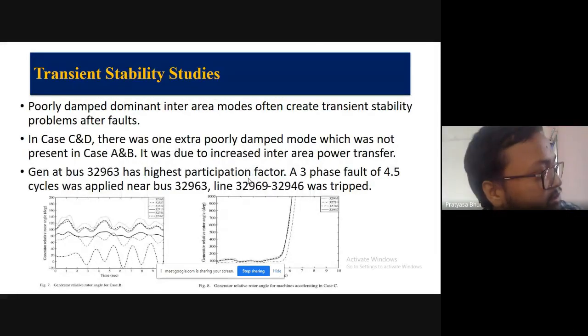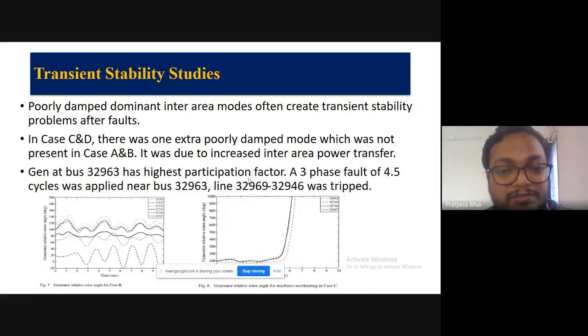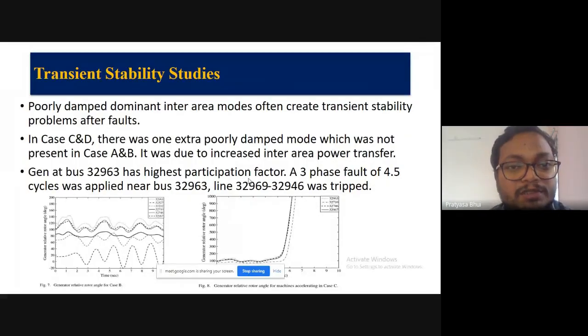Now, the study we are doing for small signal stability will help us to study transient stability in some cases, because sometimes we have weak, dominant inter-area modes where the frequency is very low and damping is poor. In those cases, sometimes if there is a fault, it excites that mode. In that case, there is a possibility that the two areas will separate and it will become transient unstable. After a fault, the system will separate and become unstable.